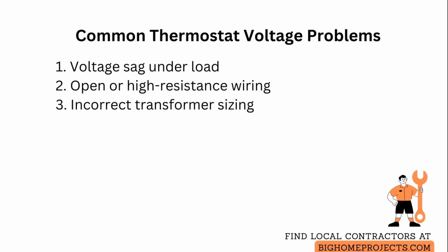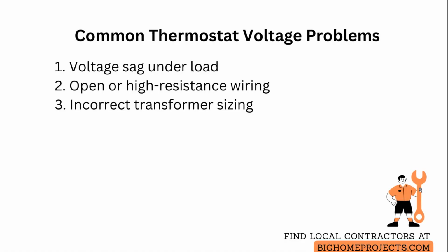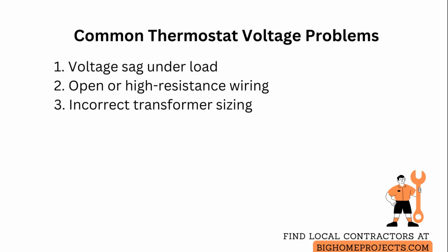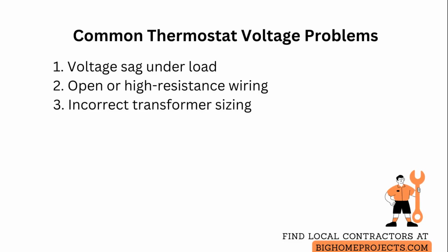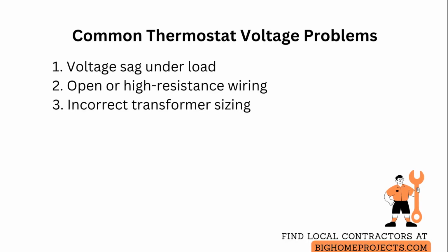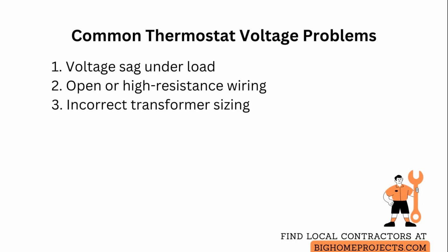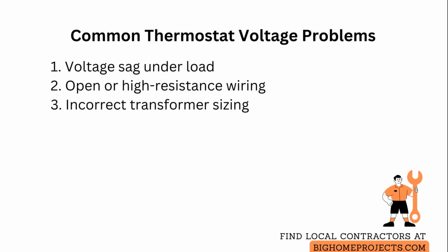Three common issues are voltage sag under load, open or high resistance wiring, and incorrect transformer sizing. For voltage sag, measure under both idle and call conditions and replace the transformer if the underload voltage drops below 24 volts alternating current. For wiring problems, remove and inspect thermostat and transformer terminations for corrosion or loose screws, then clean and retighten or replace damaged conductors.